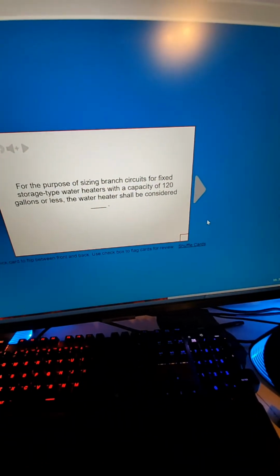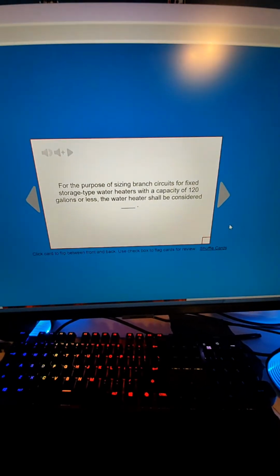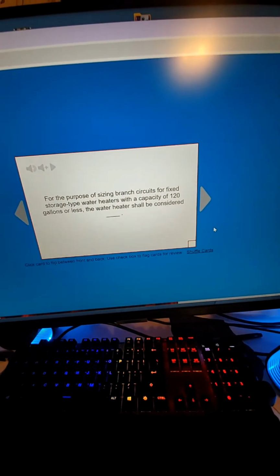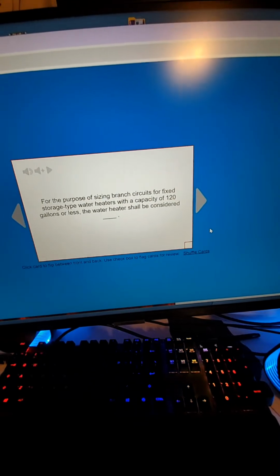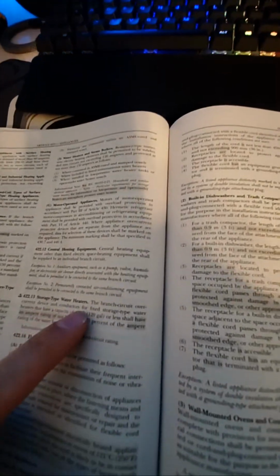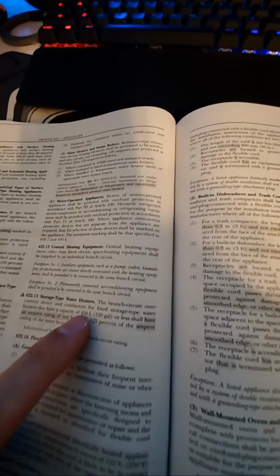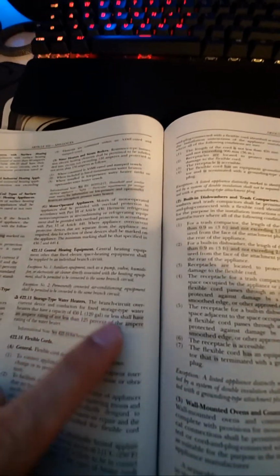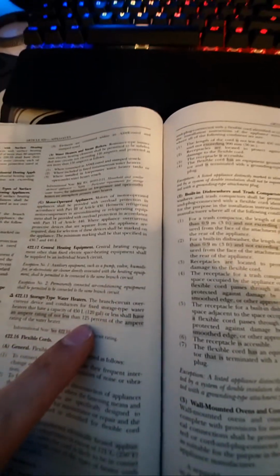Storage type, okay. For the purpose of sizing branch circuits for fixed storage type water heaters with a capacity of 120 gallons or less, the water heater shall be considered. Okay. Here's storage. The branch circuit overcurrent device for fixed storage type water heaters having a capacity of 120 gallons or less shall have the ampere rating not less than 125%.